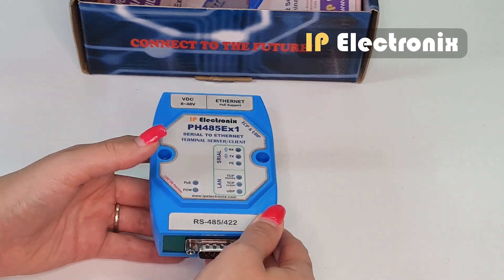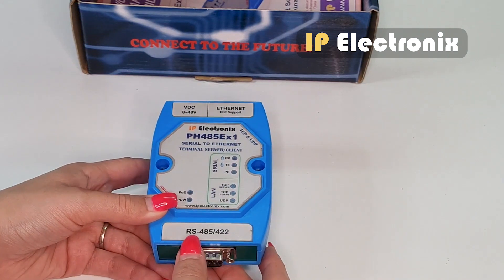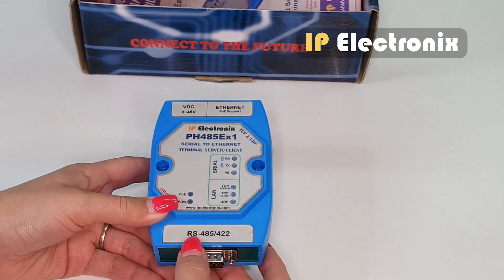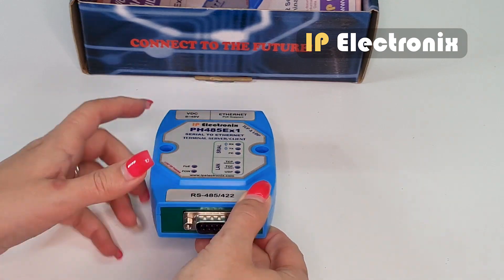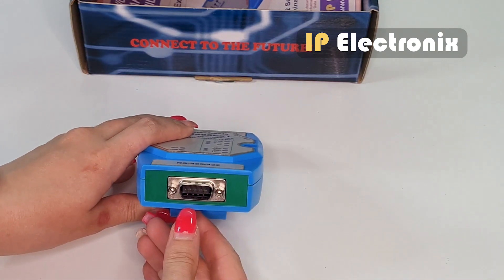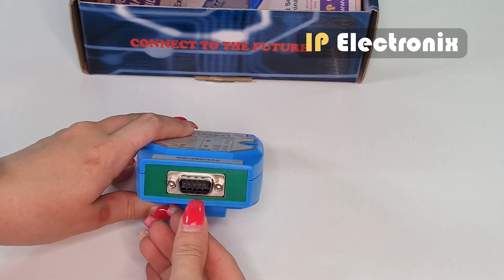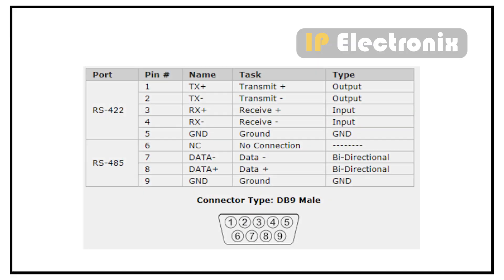At the other side, it has RS485 and RS422 ports with 9-pin DB9 male connector. On this converter, RS422 is located on pins 1 to 5 and RS485 on pins 6 to 9. According to this table, data minus signal is on pin number 7, data plus signal is on pin number 8 and GND is on pin number 9.